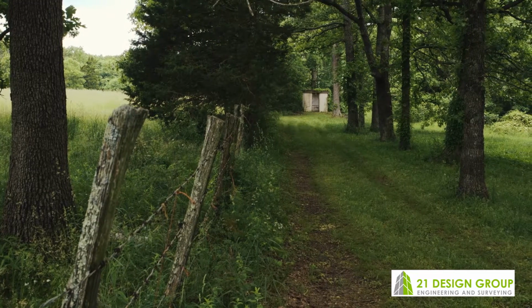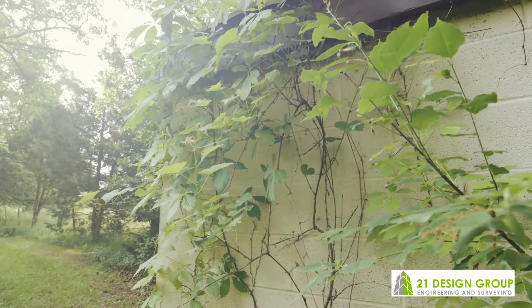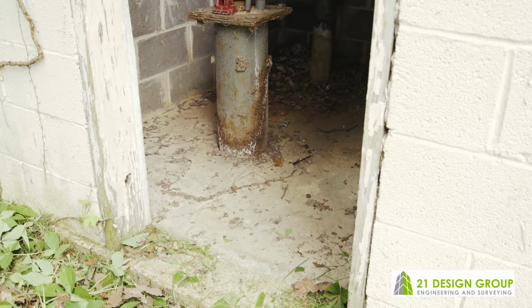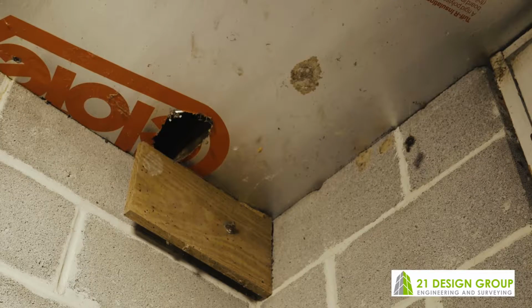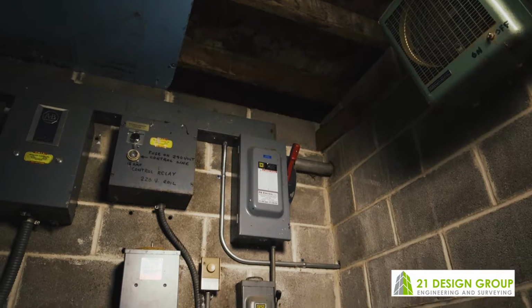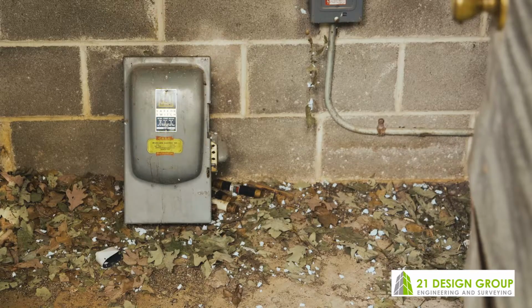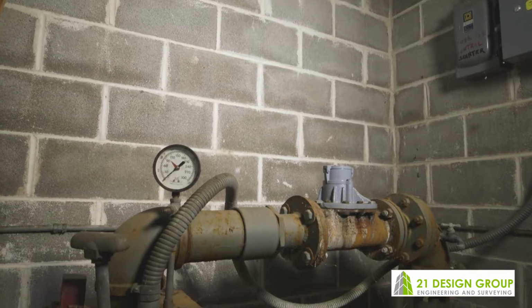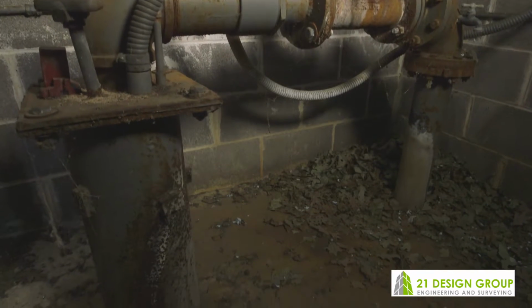Like well house number 1, well house number 2 has multiple violations. An independent electrician and water well expert found the well to be out of service and no longer viable. With this well out of operation, the system violates Missouri DNR's requirement of having 2 functioning water sources for the community. In the 2014 report, they stated that outside water hauled in by tanker trucks is the only other viable alternate water source option. The current plan to properly close this well as part of the system-wide reconstruction will eliminate the existing potential for this offline pump to contaminate the area's drinking water.